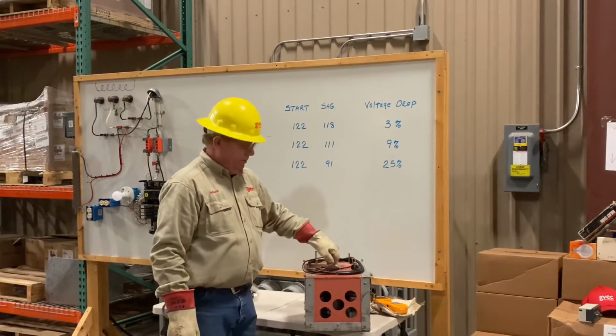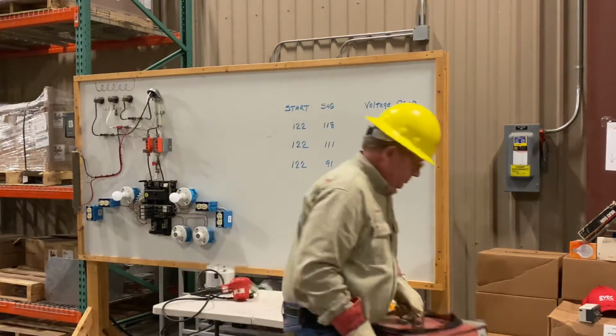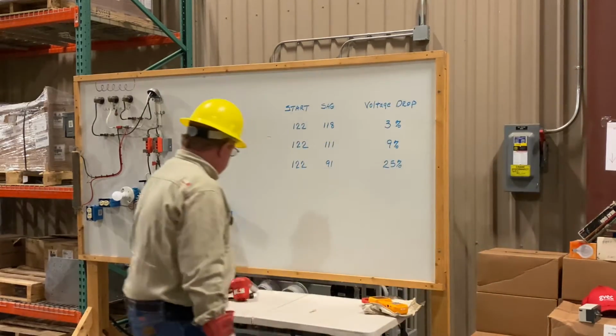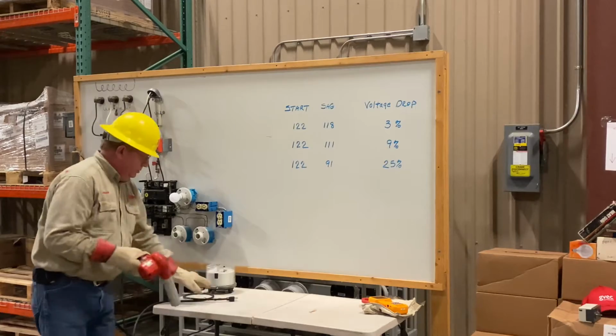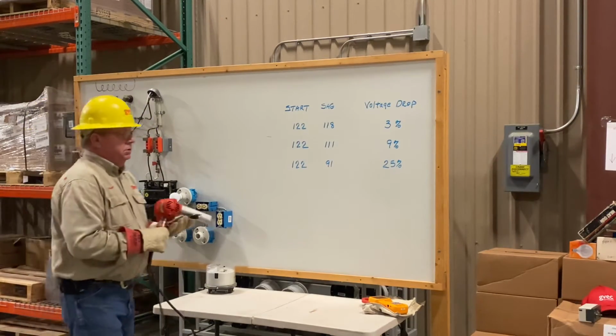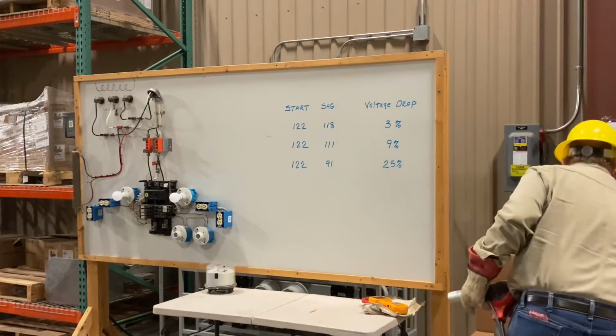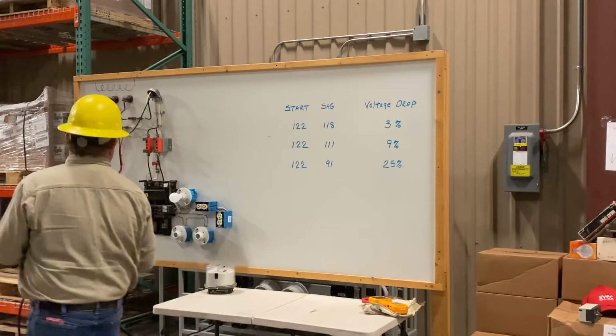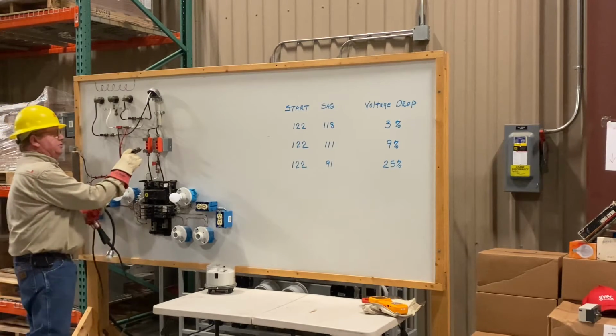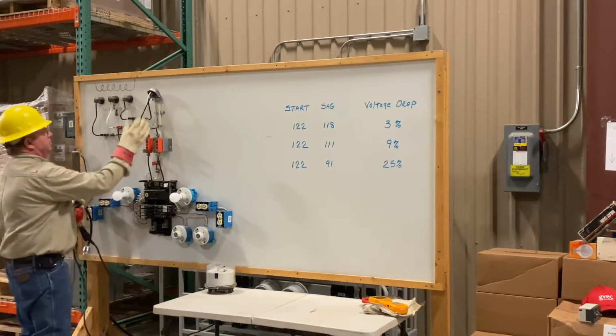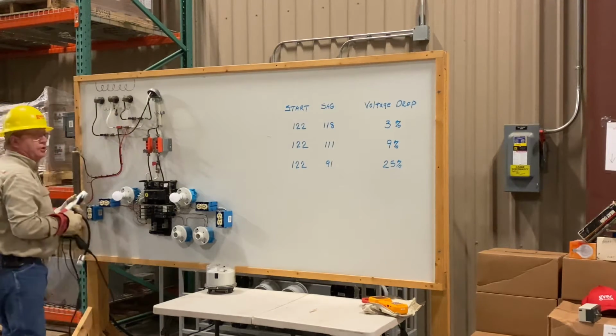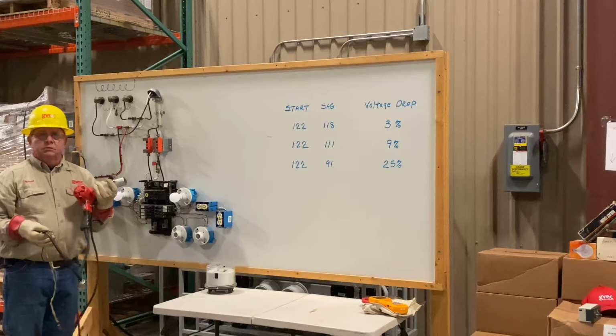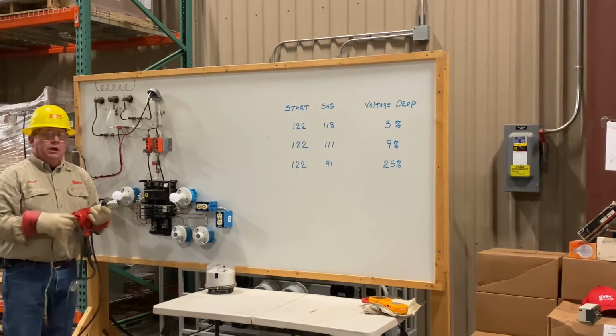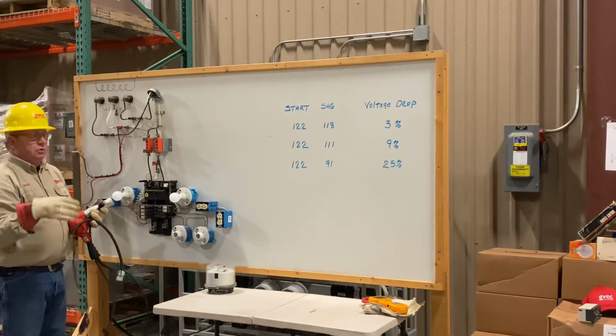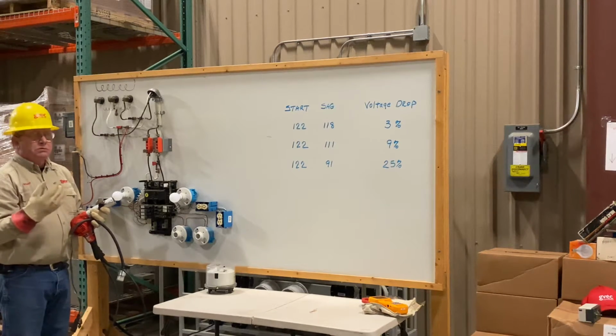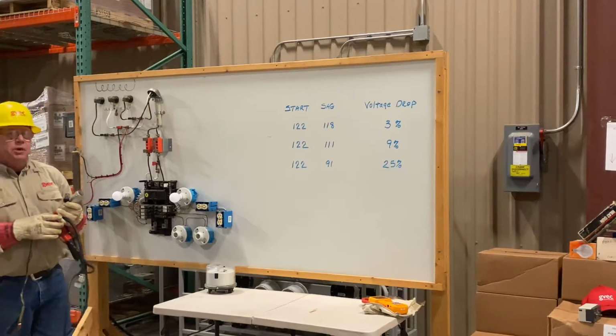You may not have this one with you. We take our source for load. We can pigtail into the meter socket, test back through the riser and back to the transformer connections, and deliver an external load that's not part of the house. We can put all of it on one leg so that we force that neutral to take that full 10 or 12 amps. Usually this is pretty effective.